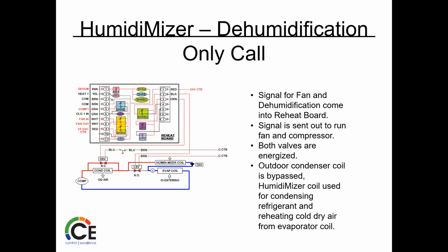Dehum call, you get fan and dehum coming in to the reheat board. Then we send a signal out to run the fan and compressors. Both of the valves are energized at this point. Outdoor condenser coil is bypassed, HumidiMizer coil used for condensing in our HumidiMizer. So again, some of the other ways we were using the condenser coil, here we're not.